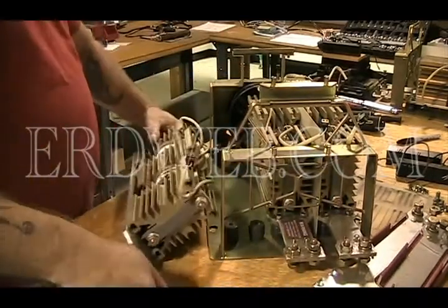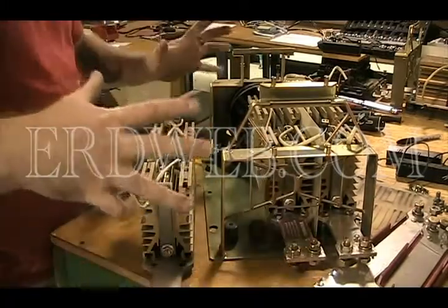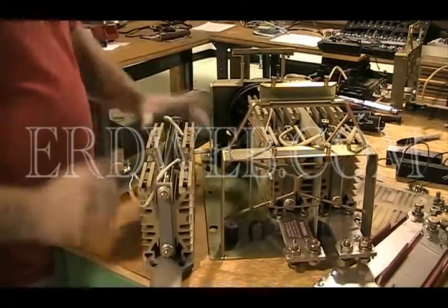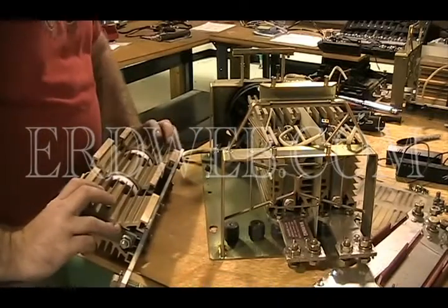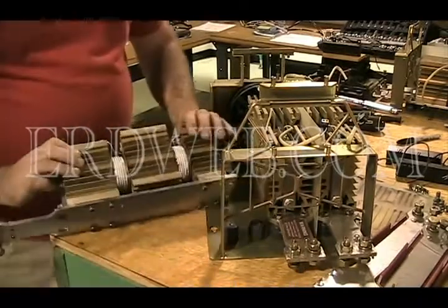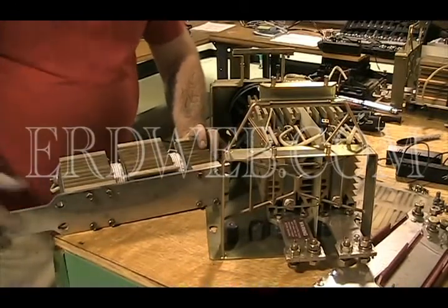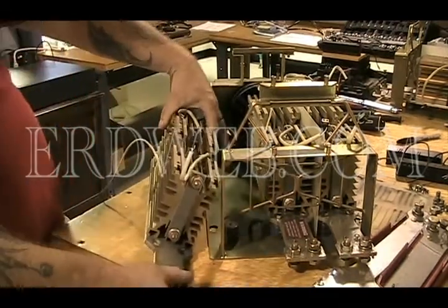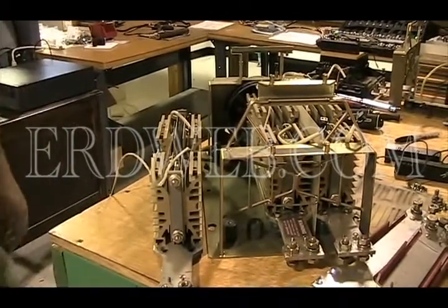That's pretty much it. These two bolts come apart, this all comes apart. You check the SCRs if it's good; if not, they've got to be replaced. That's pretty self-explanatory — it comes apart. That's about it. And then you put it all back in there and hope it works. Alright, let's go for it.